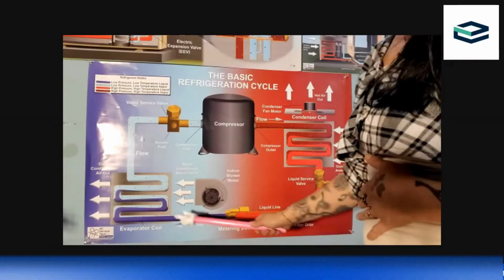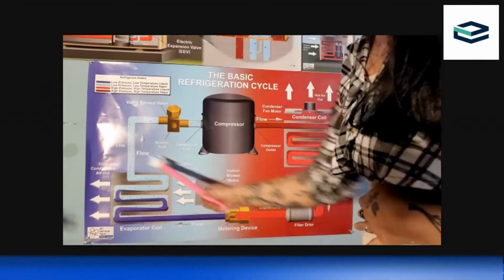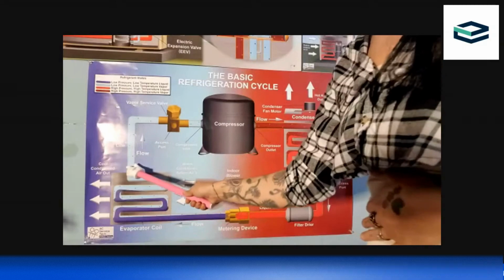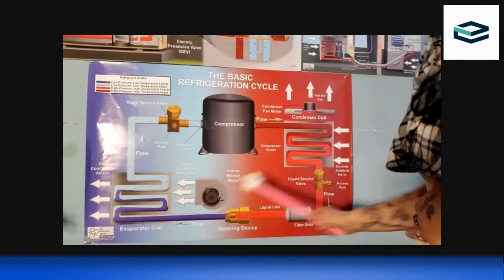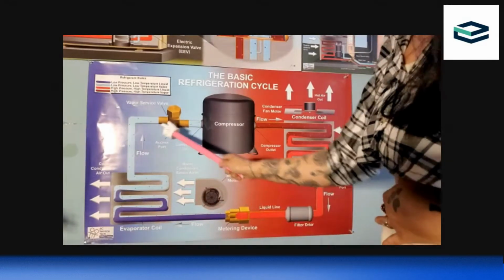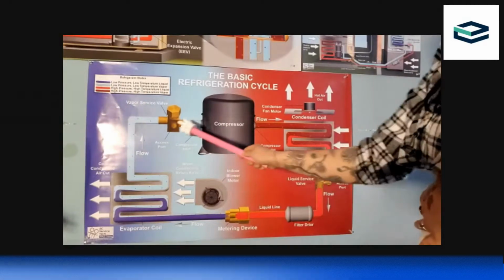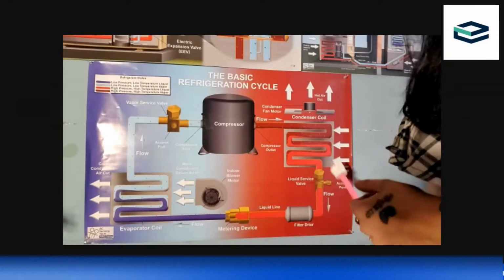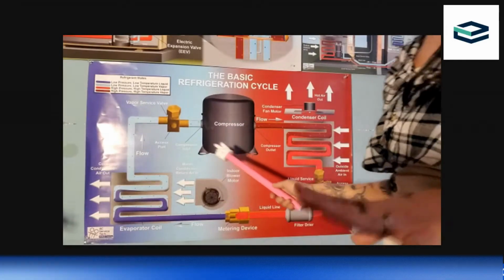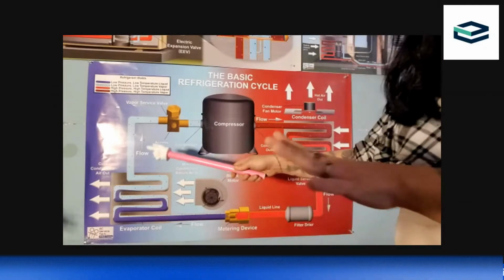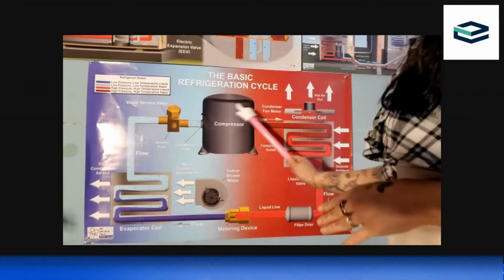And then going forward from there, we have the evaporator coil, which is exact and opposite from the condenser coil. And then we have another service port on the opposite side. As you can see, we always have service ports, 1 on each side. Sometimes you'll only have 1 on one side, and that's okay. I will teach you guys how to use that to your advantage as well. And then we're back to the compressor here.